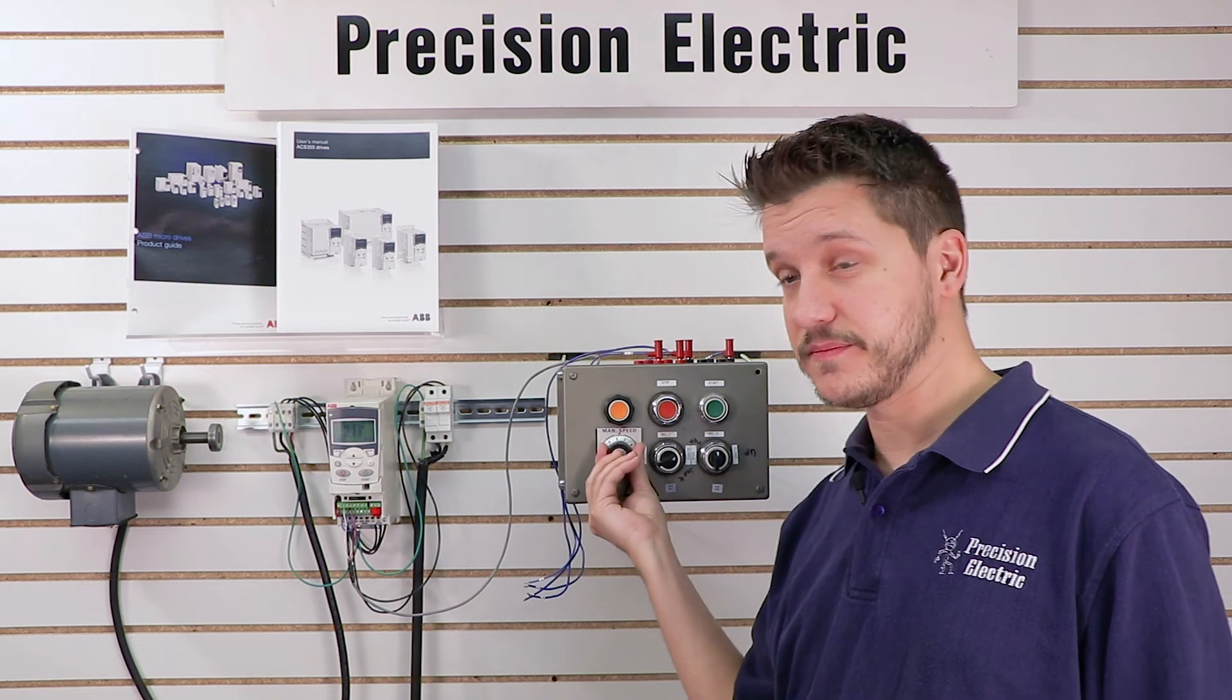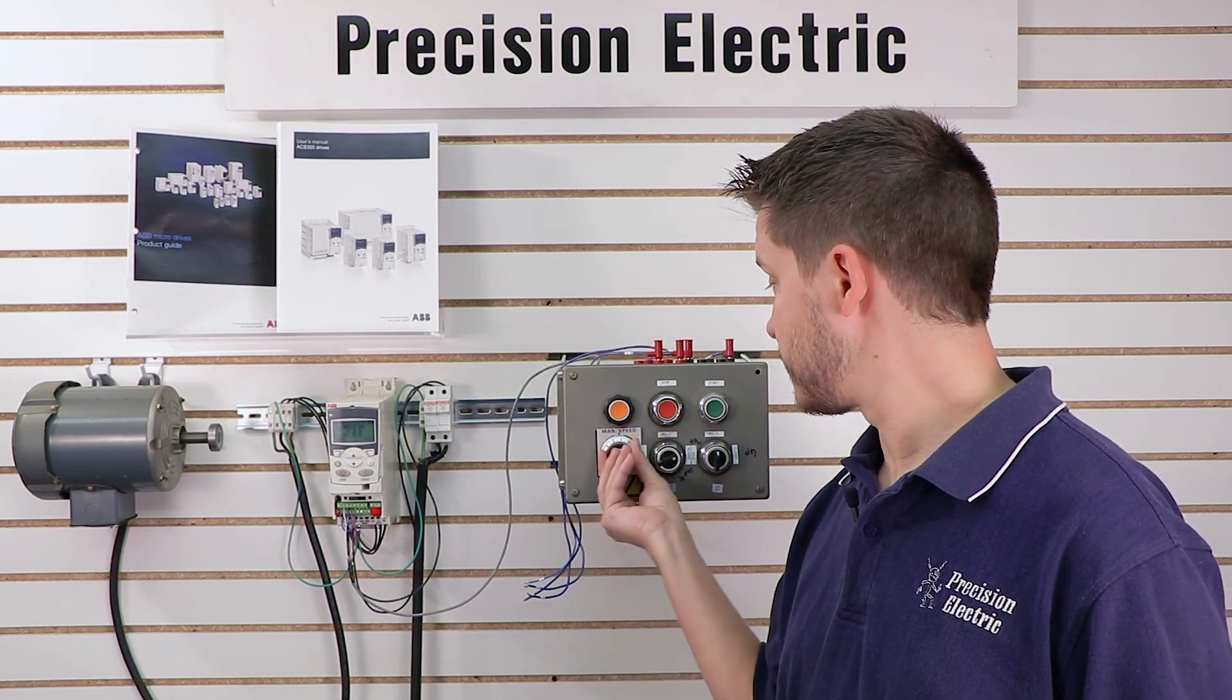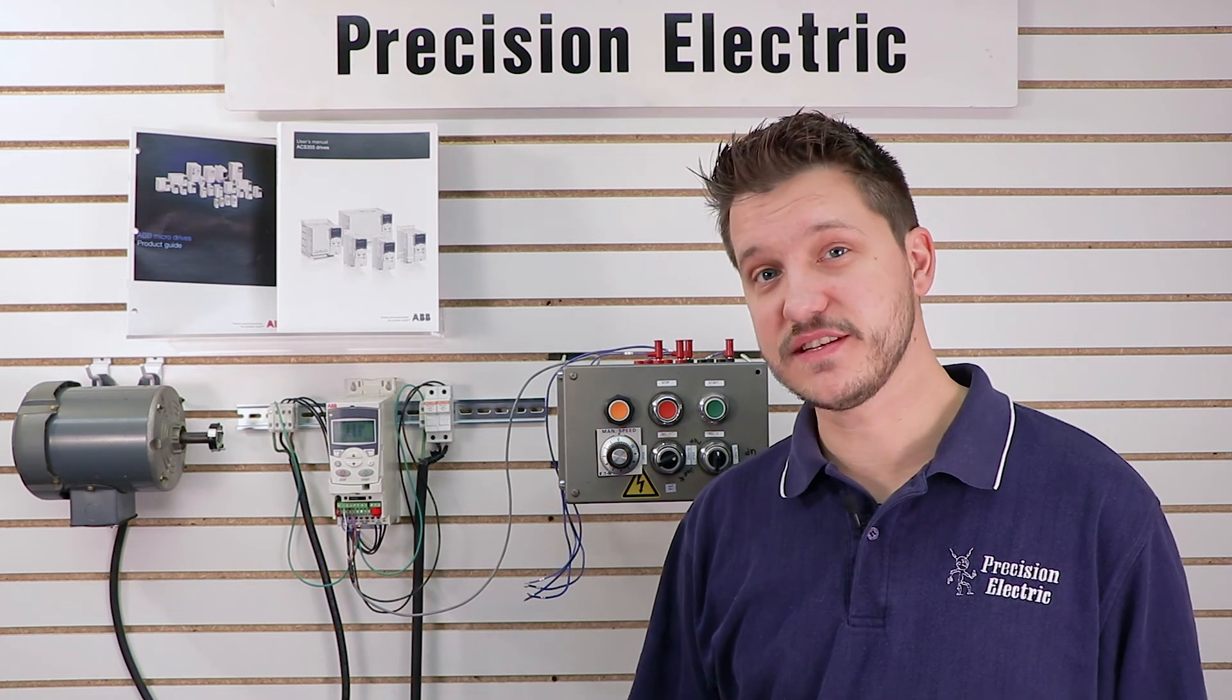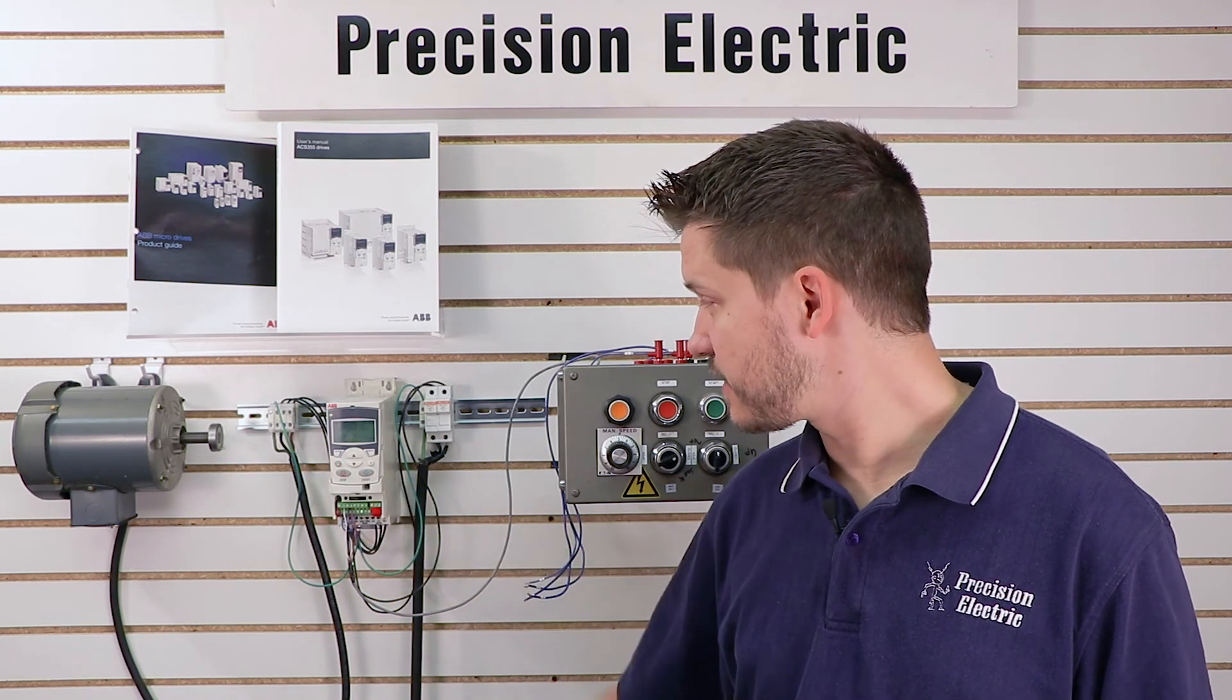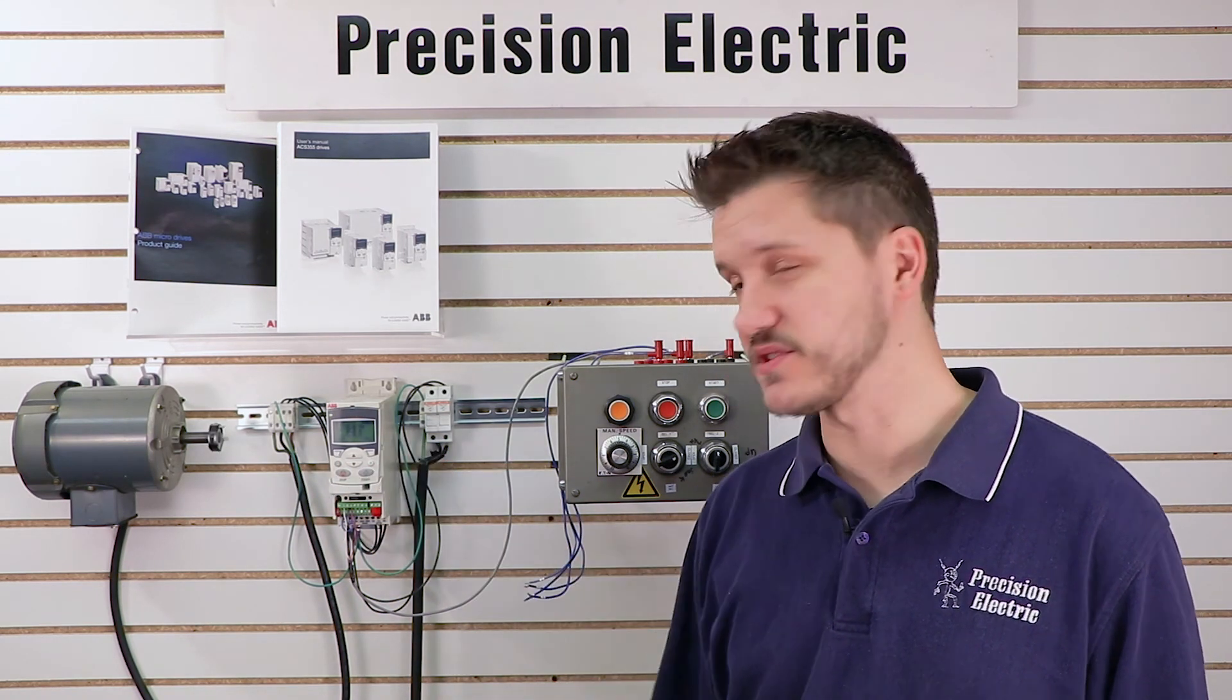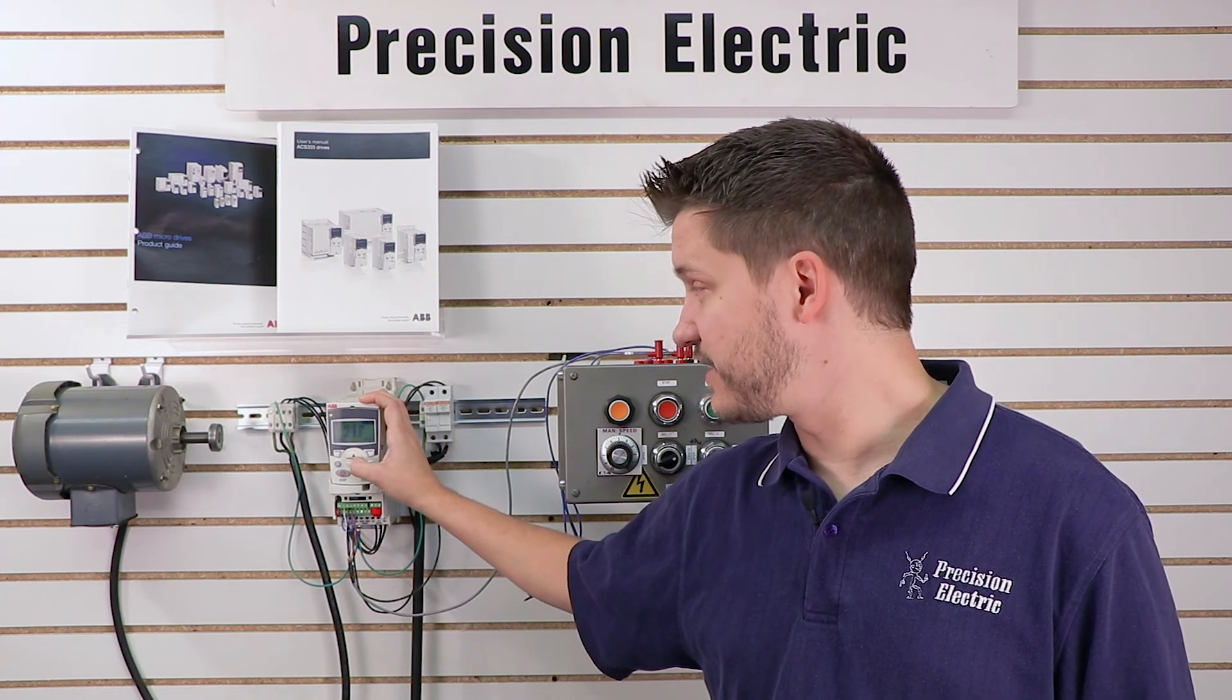So now I can actually turn it up - so there's full speed - and I can turn it all the way down if I want. It just sits there. If I want to switch back to my keypad control, I can just press local remote again, and I'm actually back in keypad control. I want to start it, press the start command, and I can now use the up and down arrow keys that control the speed on the keypad.